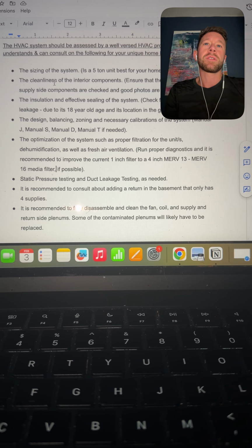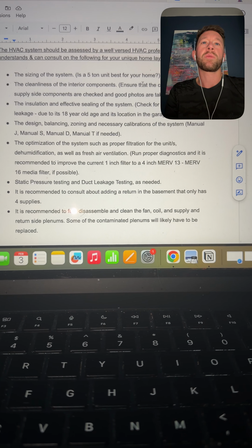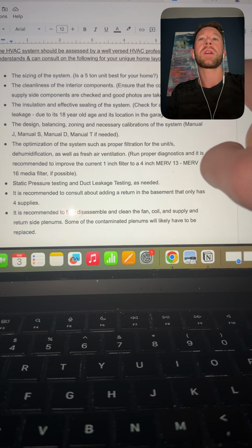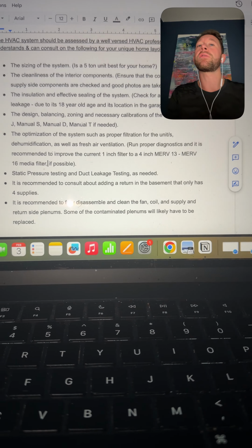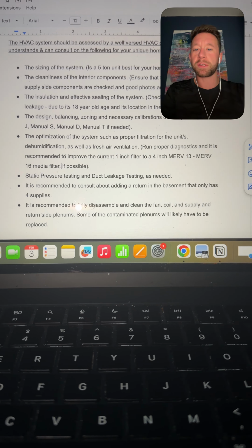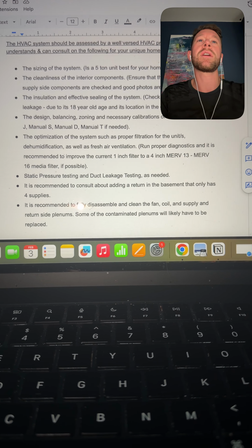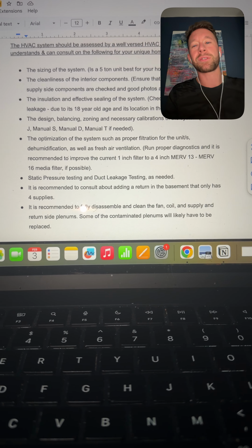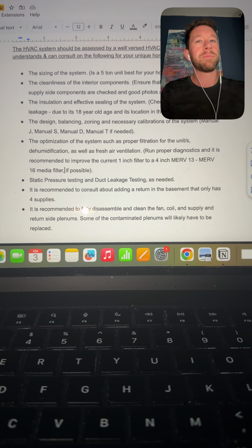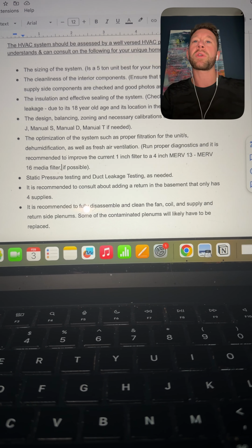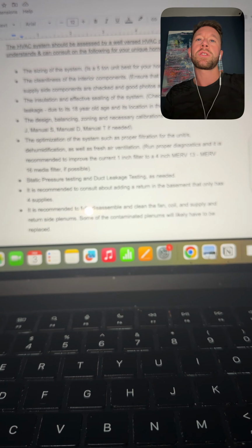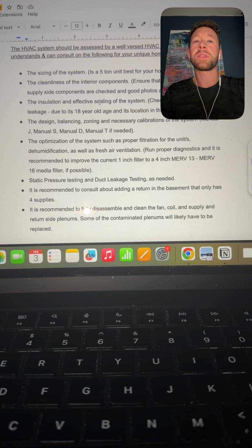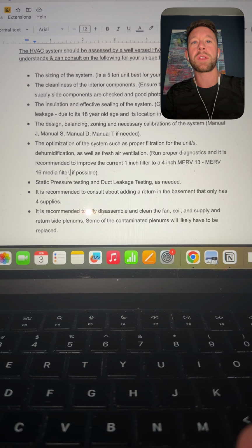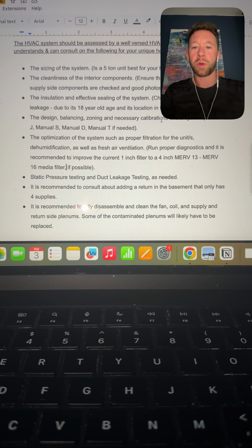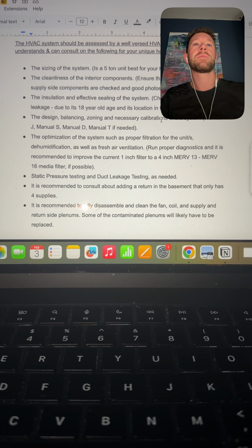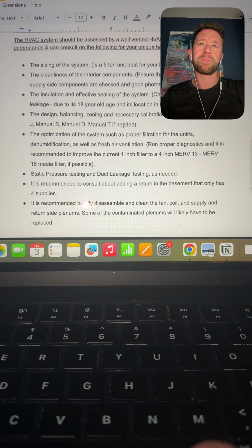The cleanliness of the system should be checked in interior components. Ensure that the coil and all other inaccessible supply side components are checked and good photos are taken, because from a distance on this virtual consult, I could not see inside the supply side, but the return side looked dirty enough. 18-year-old unit, probably pretty dirty. And they've had humidity problems, not surprising. The insulation should be checked and the effective sealing of the system. If we have significant air leakage, that's why they should check for that. That can cause pressure problems and very, very dusty, compromised indoor air quality.